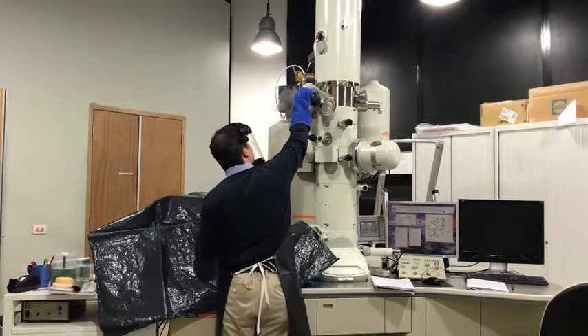Bit temperamental sometimes. As it boils off, the liquid nitrogen spits. So we fill it until we get a little bit of an overflow. That's why we need the plastic sheet. Without the plastic sheet, if we get some liquid nitrogen onto some of the more sensitive parts of the microscope, you can get thermal cracking, and that's not great.